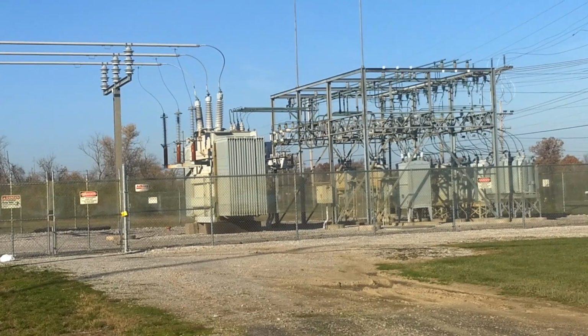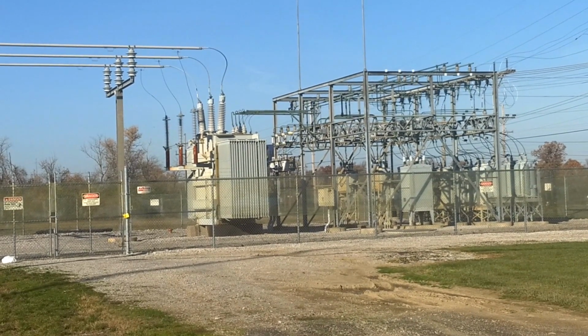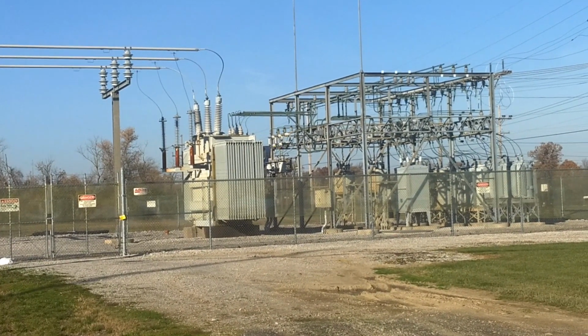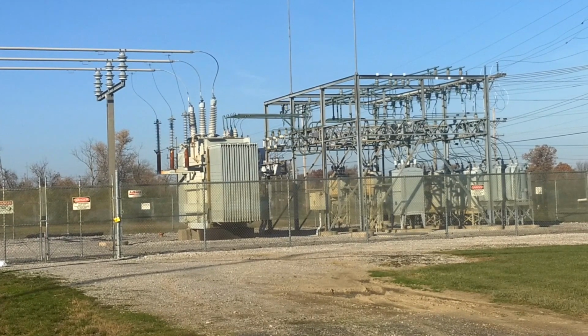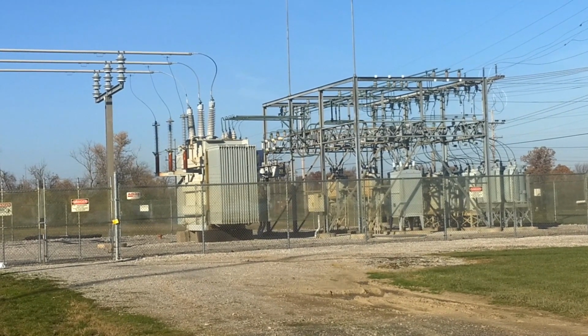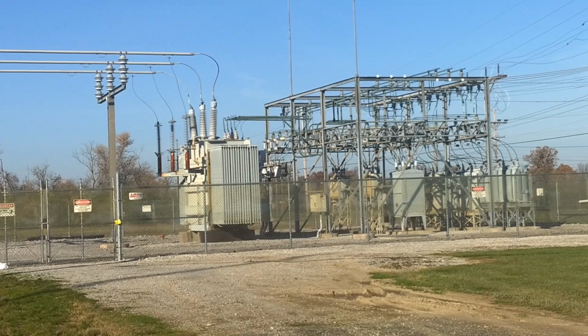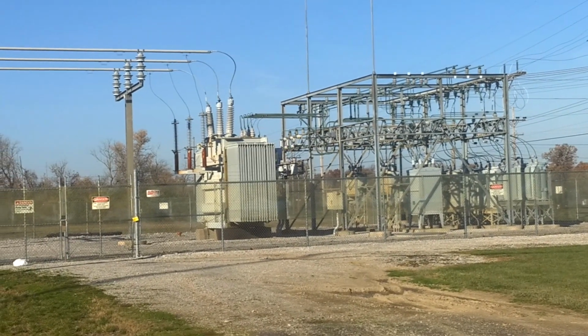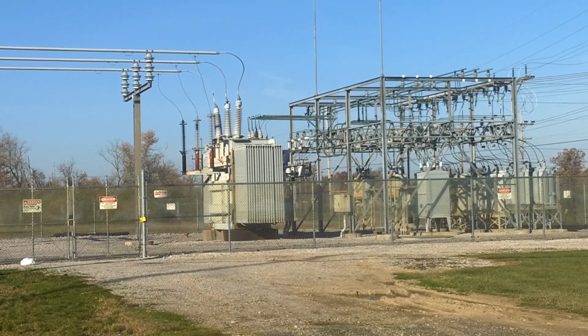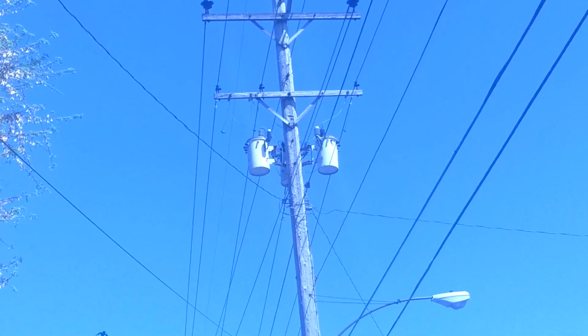The transformer shown here is a step-down transformer. It's used to reduce voltage from transmission lines, which may be at several hundred thousand volts, down to tens of thousands of volts, which is then fed to transformers like these, where the voltage is reduced again to the nominal voltages that enter businesses and homes.